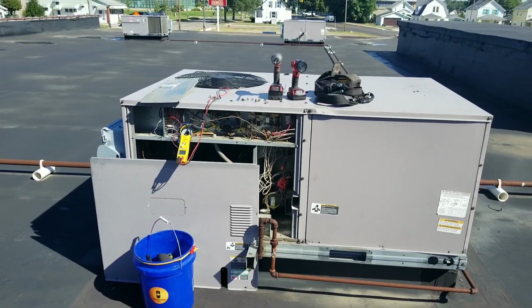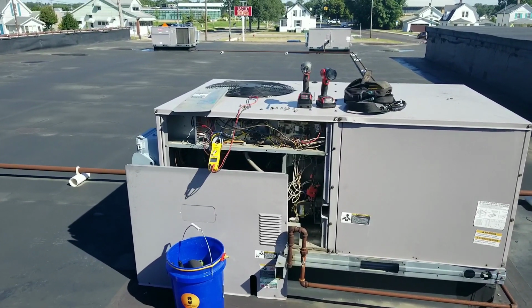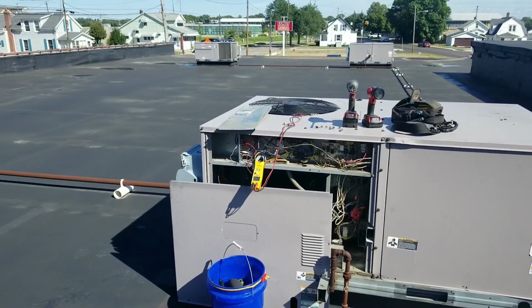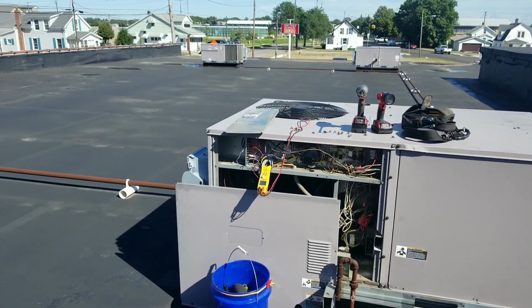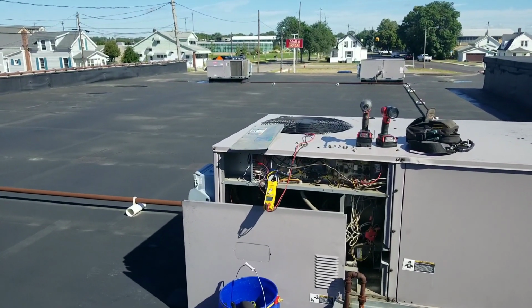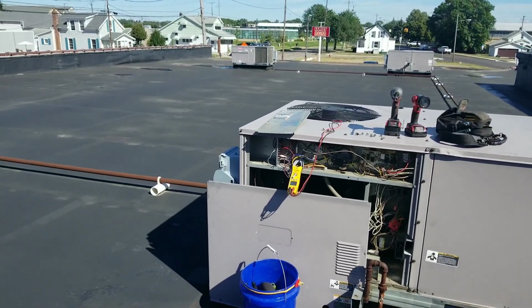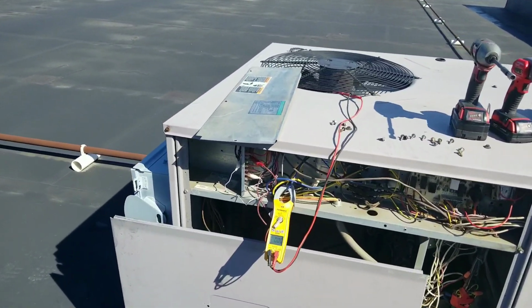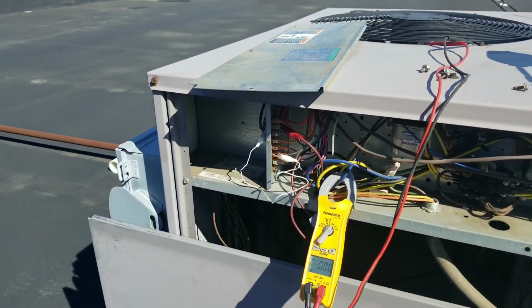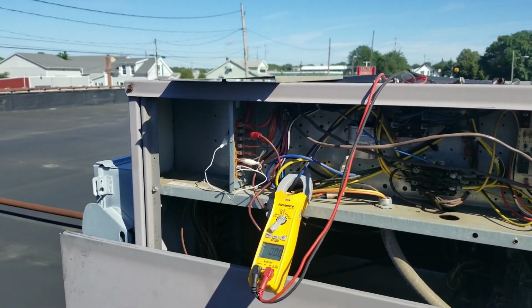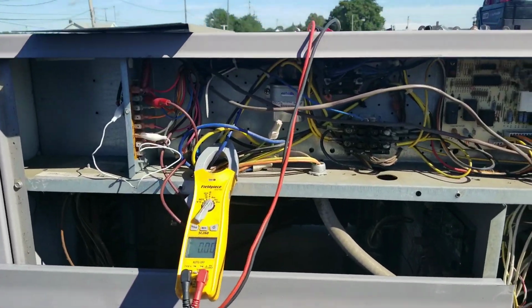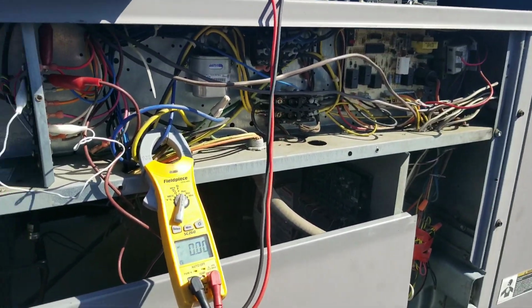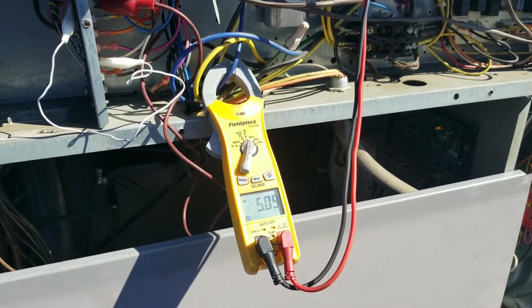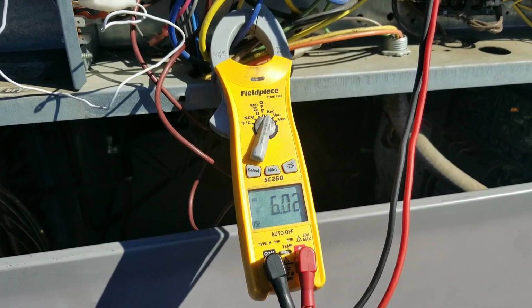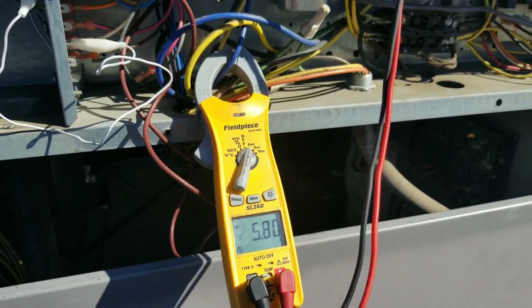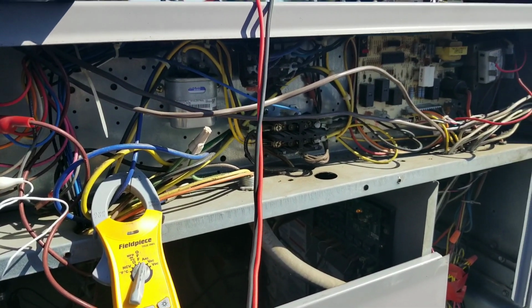Now, since we can't find any shorts to ground, I'm gonna power it on, let it run in cool mode, and see if maybe my compressor is drawing locked rotor amps, which could trip my breaker. So I got my amp clamp all set up. I got my thermostat jumpered out to go directly into cool mode with the indoor blower motor running. So let's get to it and see what happens. Compressor is on, pulling 5 amps, which is not bad at all.